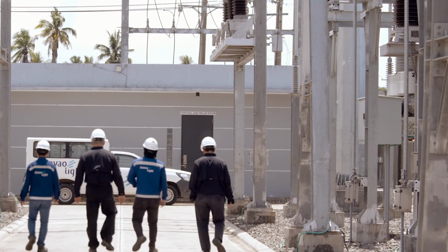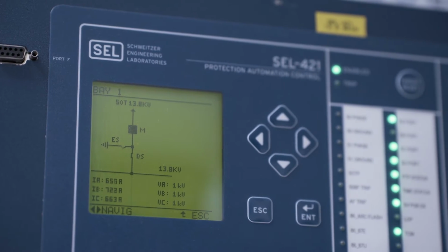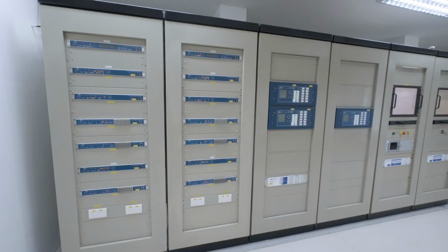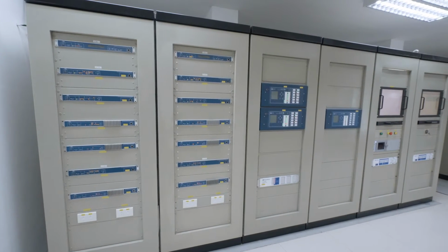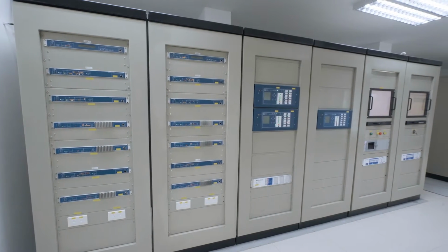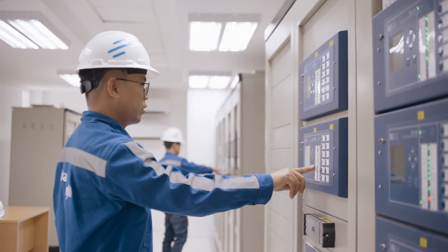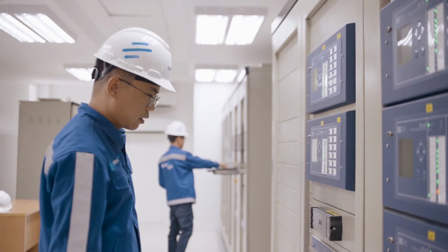We ensure that the protection system is really dependable and reliable by making sure that the IEC 61850 network is reliable also. So we implemented GOOSE communications in parallel redundancy protocol.